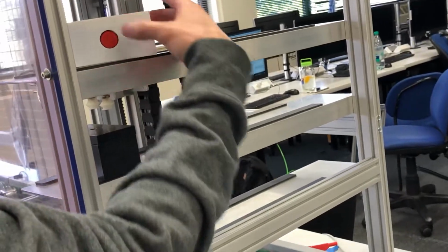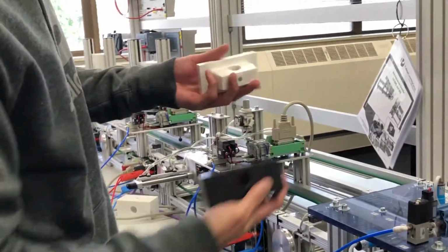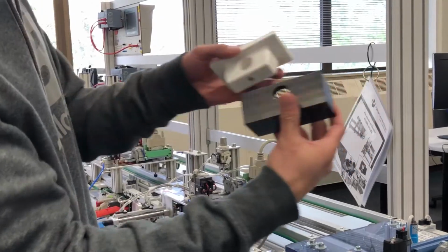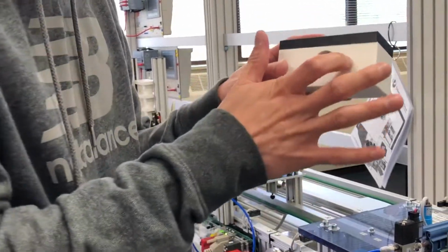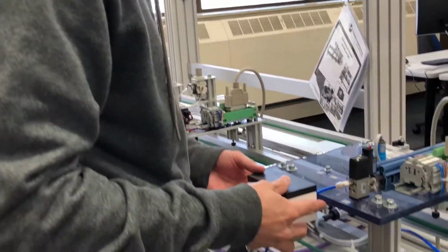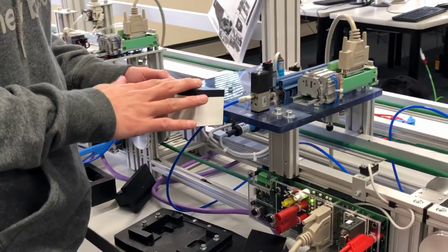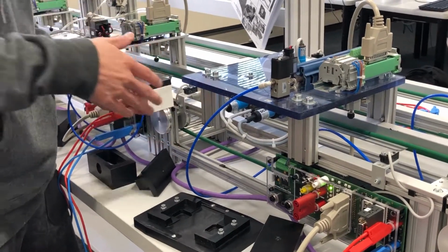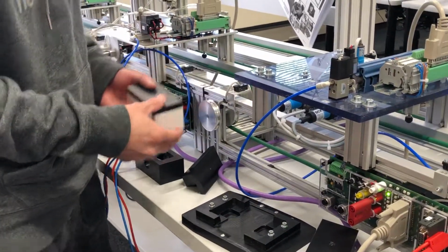And you can see here all the products with the same color, the top one and the side one, the same color, the right product. If there's something wrong with manufacturing, a different color coming in, for example the white on top and the black on the side, or the other way around, it means something is wrong with the product, right? So when it comes to station 4, the sensor will recognize something wrong and stop the whole manufacturing and reverse the part back to here, so people can come and pick up the wrong one, right?